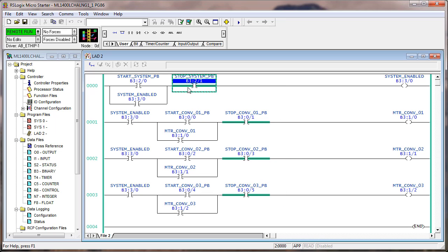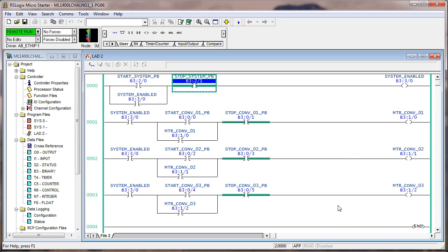And you see the instant that I broke the logic here and dropped out the seal-in bit, then all these bits went false and turned off all the conveyors. Did any conveyors stop? Yes. How many conveyors stopped? I said all of them instead of 2, just in case you had restarted the one that you already stopped. Did any return to the on state when you toggle the stop push button on? Meaning, when we toggled this off, and the question is, when I did this, did any of them start back up again? Again, that's obvious, but we're emphasizing that.